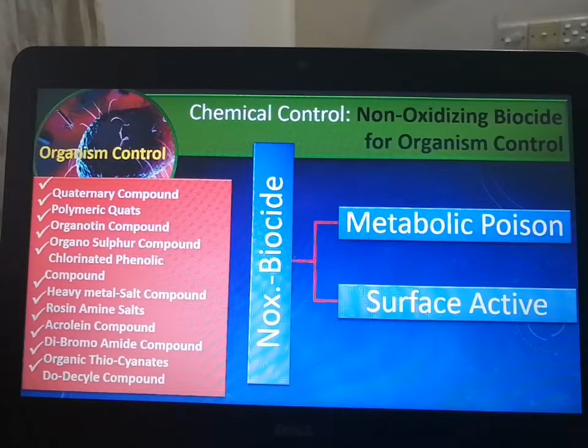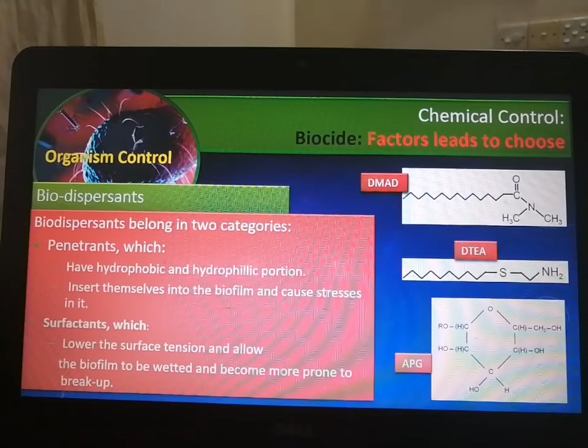Again, we confirm that the biocide chemistry shown in the left side table alone can't control, can't perform perfectly, effectively, or efficiently. We must have some biodispersant or dispersion agent with it, either in the same formulation or as independent chemistry, to help the biocide work perfectly, to kill the bacteria, to attack the bacteria surface. Unless the bacteria surface is clean, the biocide can't work on the bacteria cell. That's why combination is very important in the system.